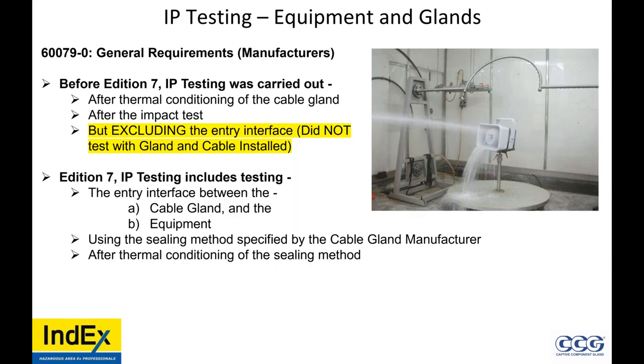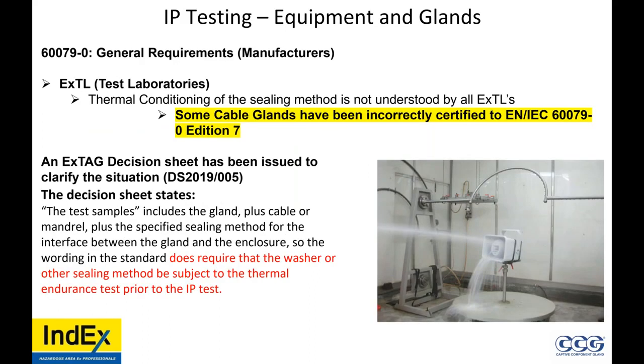So after also thermal conditioning of the seal. What that means is that they're heating up the IP washer. So if it's nylon, plastic, it can probably handle that heat. Can a fiber IP washer perhaps handle the heating and the water on it? I'm going to call that into question, which we'll see in later slides. So, under the old edition, thermal conditioning of the sealing method, the IP washer requirement, was not understood by some EXTLs, test laboratories. So some glands in the industry have been incorrectly certified. We have evidence of this. So not all glands are equal.